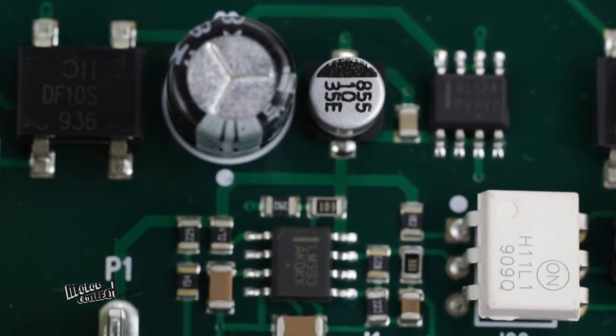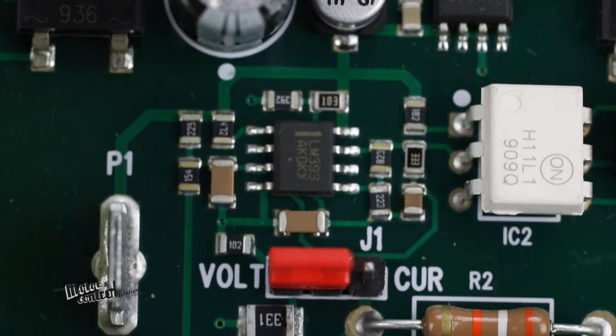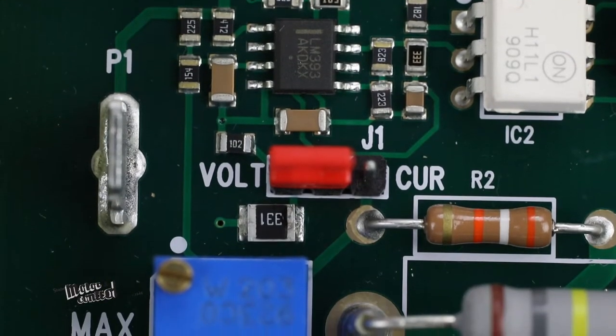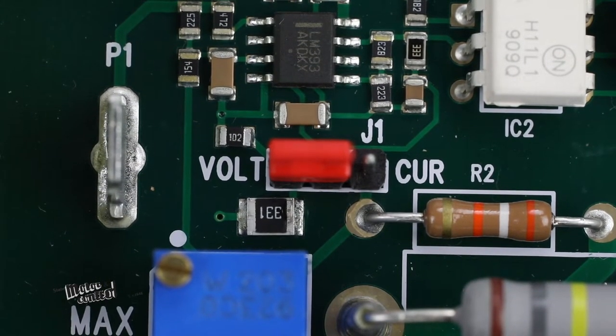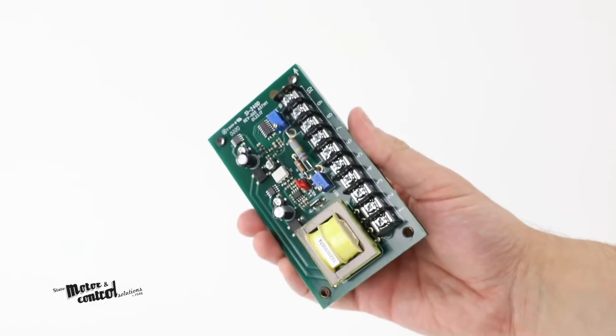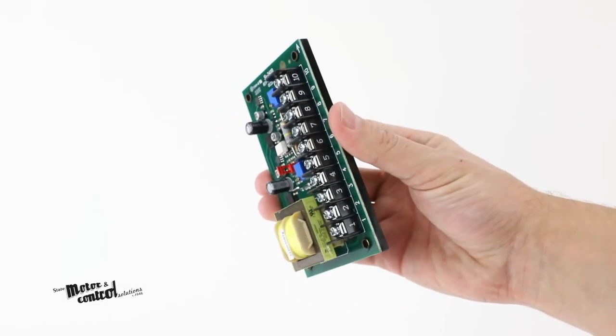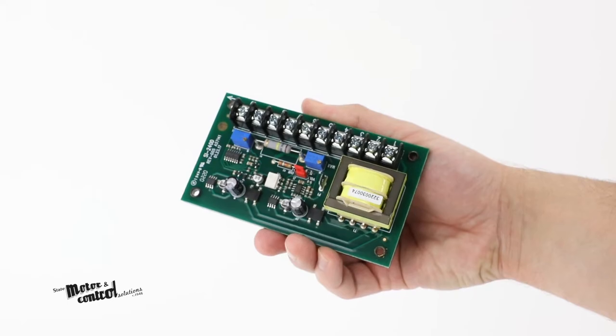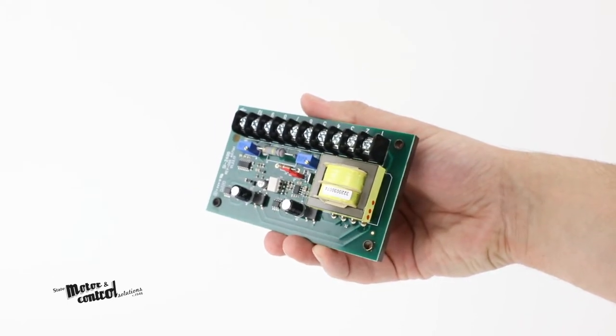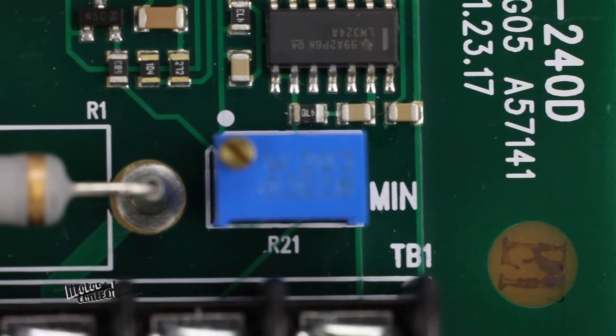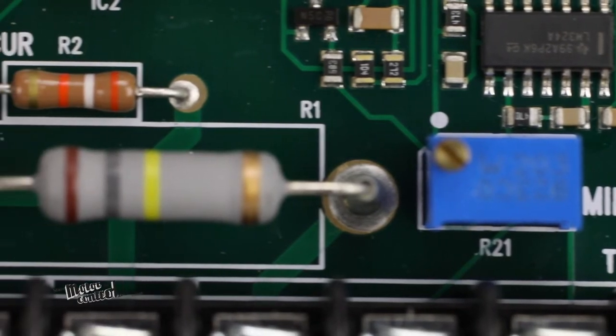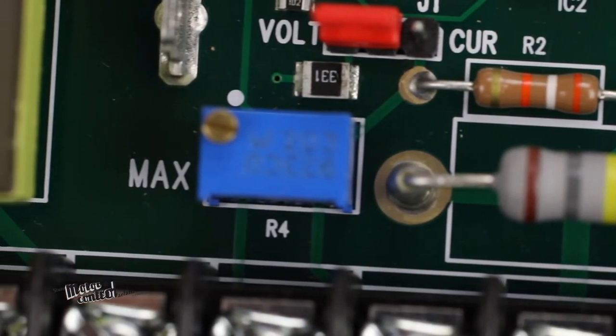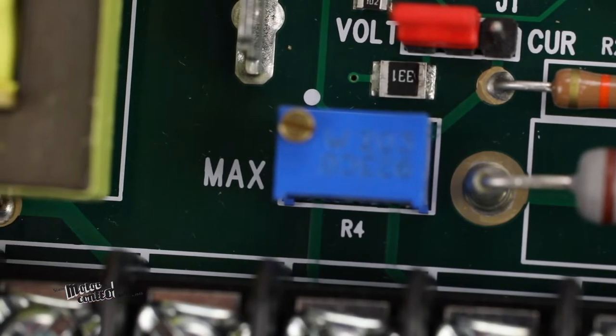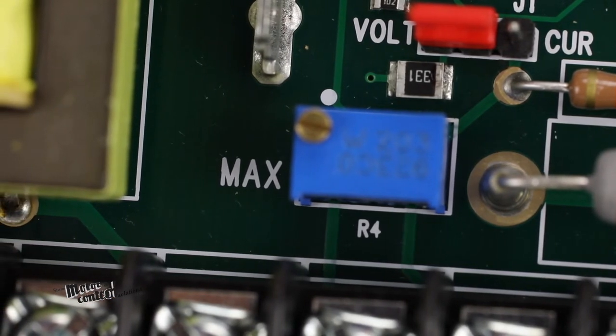Its built-in voltage current jumper is used to change the signal isolator from a voltage to a current input. The KBSI can also be controlled with a 5K ohm potentiometer in lieu of a signal input. The control is supplied with two multi-turn trim pots, min and max, which are used to scale the input and output signals to the desired level.